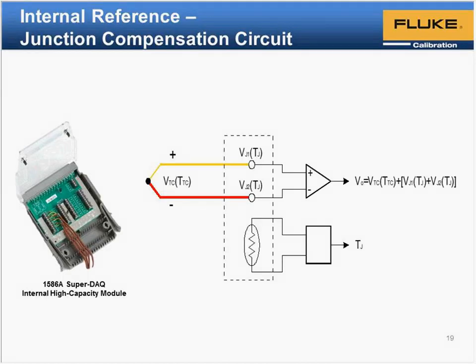And here's an example of a circuit where thermocouple wire is connected directly to a meter, and the meter has copper connectors inside of it. But that's where the junction is. We have to measure the temperature as best as we can. So there's a temperature sensor here right next to the connector, and it tells us what the temperature is. The meter takes that temperature into consideration and basically compensates for it automatically to give you the correct reading on the display.